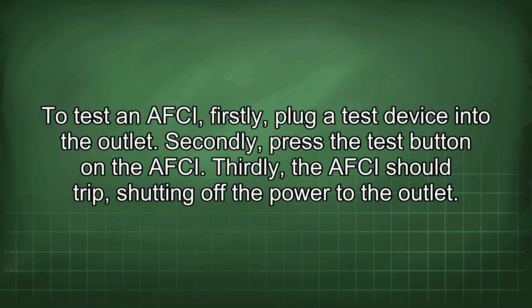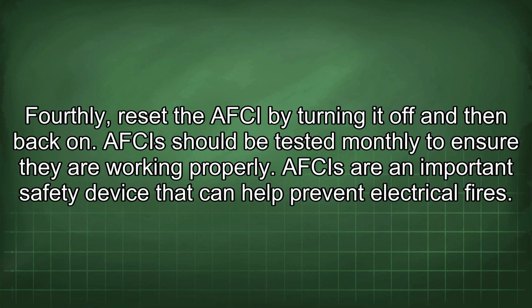To test an AFCI, firstly, plug a test device into the outlet. Secondly, press the test button on the AFCI. Thirdly, the AFCI should trip, shutting off the power to the outlet. Fourthly, reset the AFCI by turning it off and then back on. AFCIs should be tested monthly to ensure they are working properly.